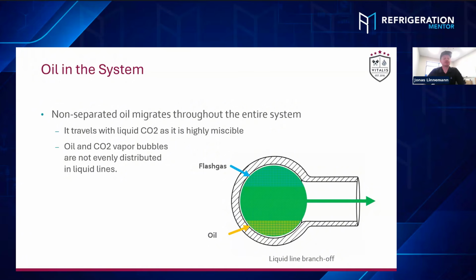It is a big difference, because if you have basically a one loop system where you supply the liquid and the suction lines all over the supermarket installations or the warehouse installations, these effects are bigger. So you need to consider the branch offs way more precisely. If you have a valve manifold station to supply 40 different loops into the entire building, then these branch offs are very concentrated on a very small distance.